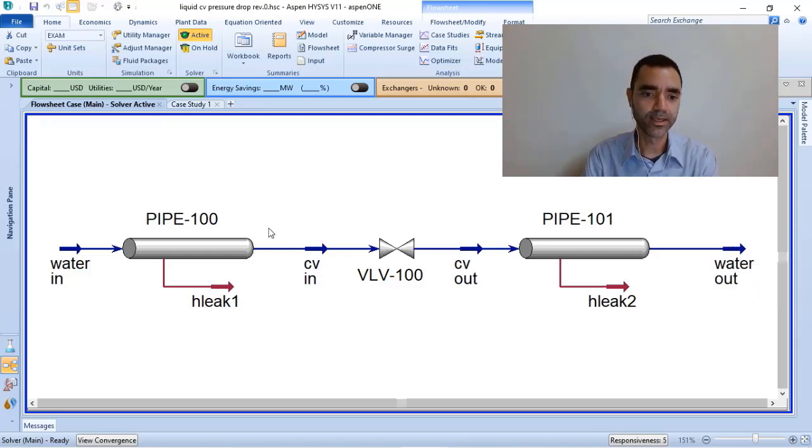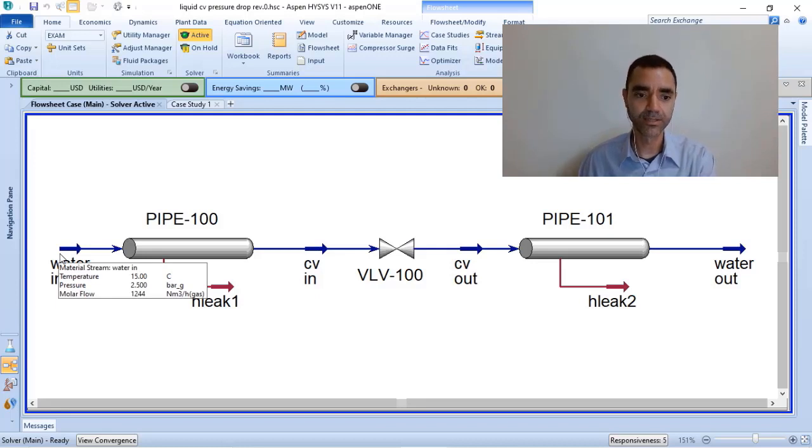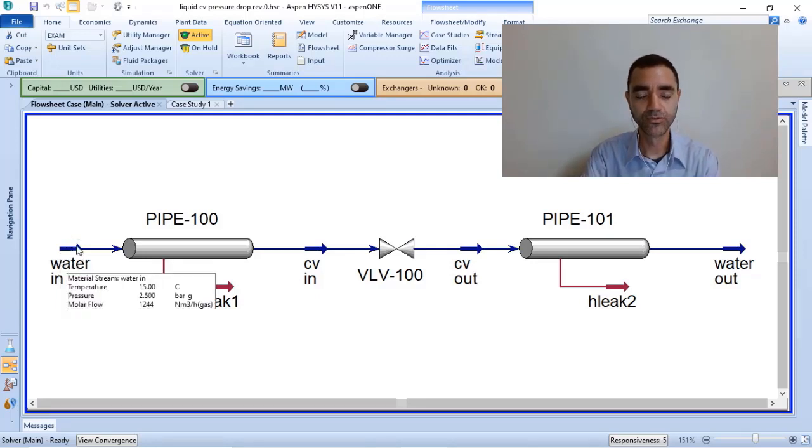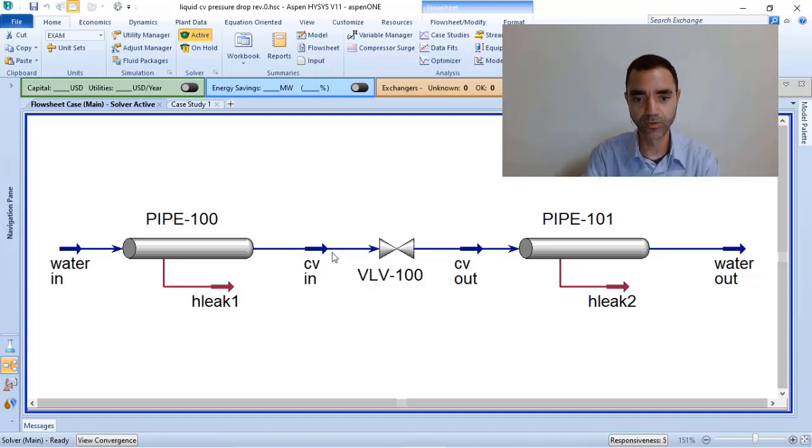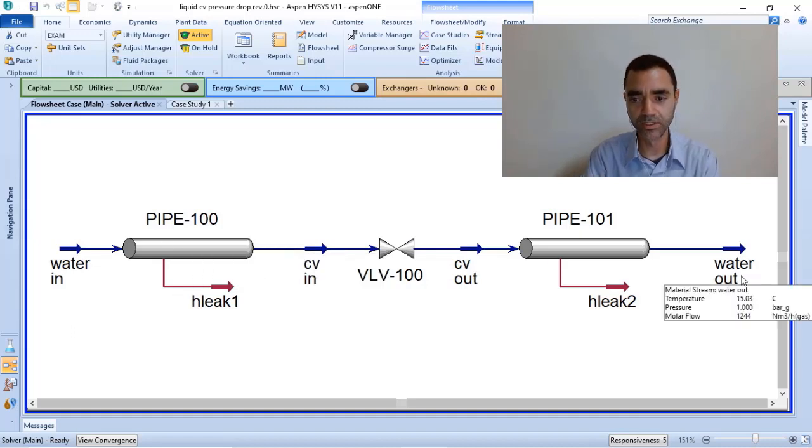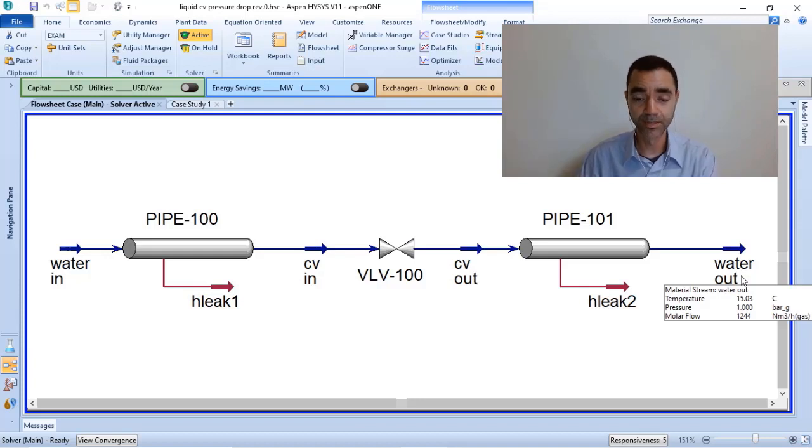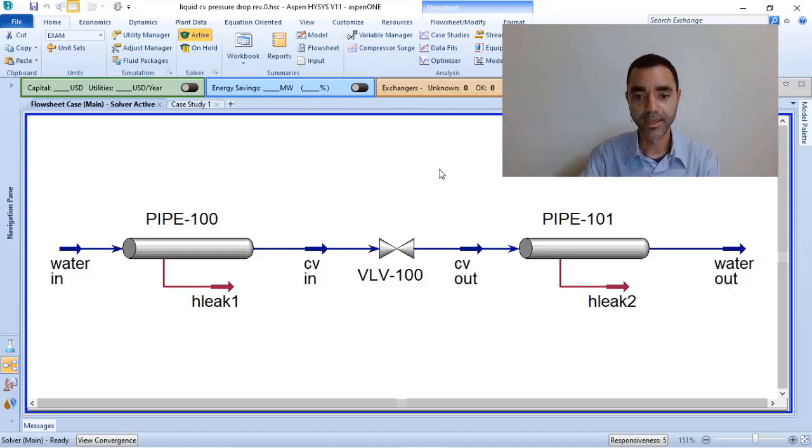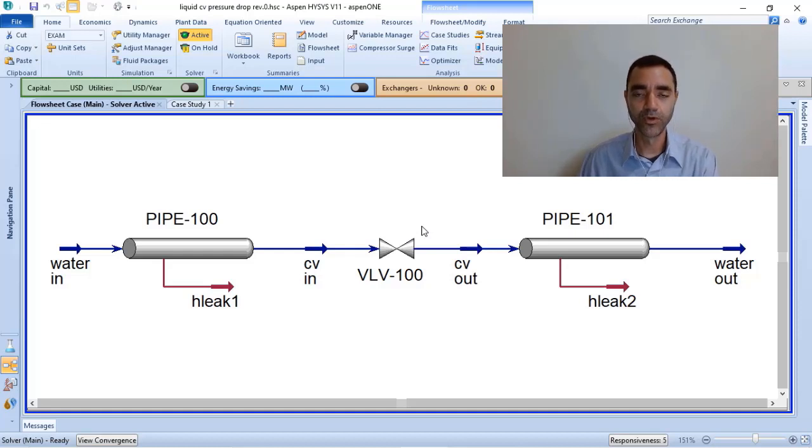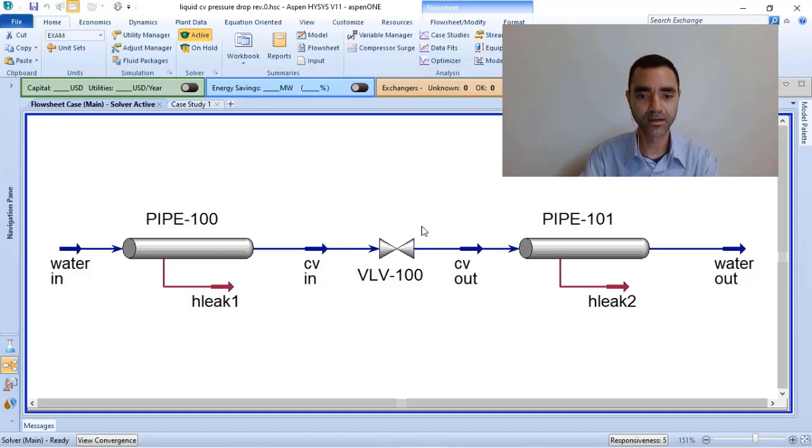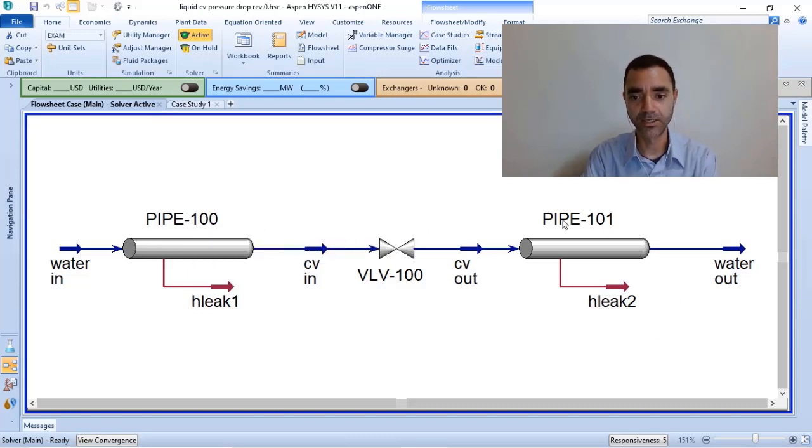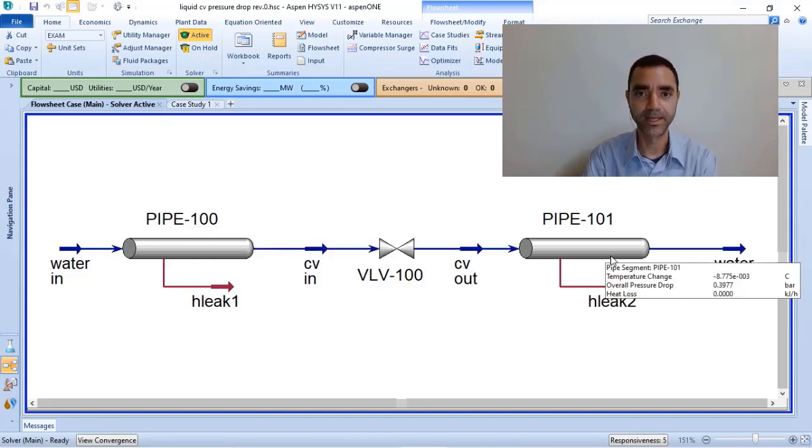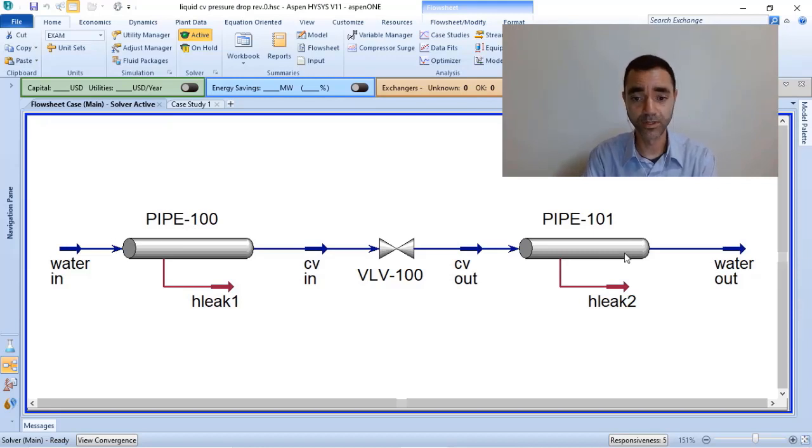We have the source of pressure that depends on the system you will calculate to give you enough energy to flow the fluid through your pipelines from point A to point B. And the available pressure drop in the valve will be a consequence of the pressure losses in your pipeline from point A to point B.